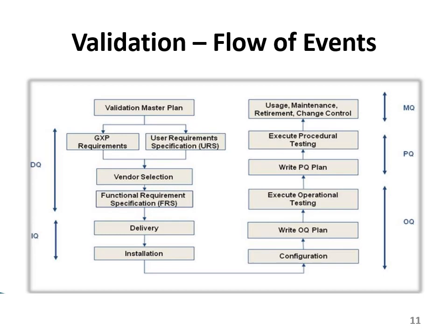So after installation, OQ, that is operational qualification, that you are going to start the operation on your machine. So configuration: after installation, you have configured that everything is okay and you are settled with the machine or equipment, and then write the OQ plan, how to operate it. Write it down. It will be easy. It will be not only easy, but it will be better for the machine and for yourself and for the process, all the things.